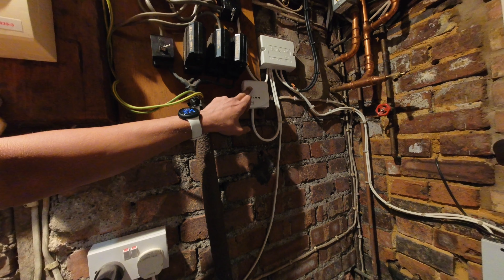I was here about a year ago to replace the wireless cylinder stat. Upstairs, since it's a system boiler, they've got a hot water cylinder and a wireless cylinder stat which stopped working, so I fitted an EPH one last year to get their hot water running again. Now I'm back this year to get this boiler fully serviced. Boiler's switched off, I'm going to go outside and do a tightness test, then crack on with this.